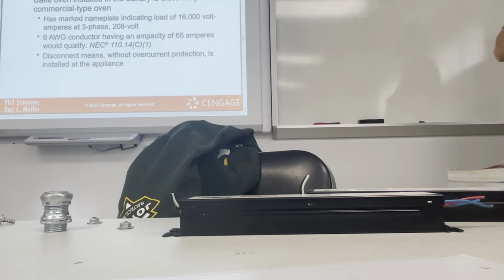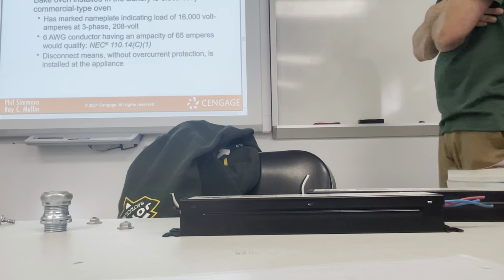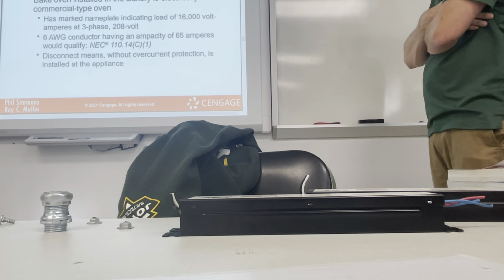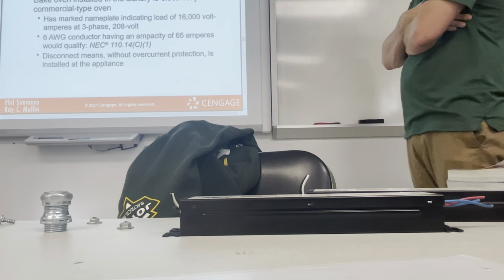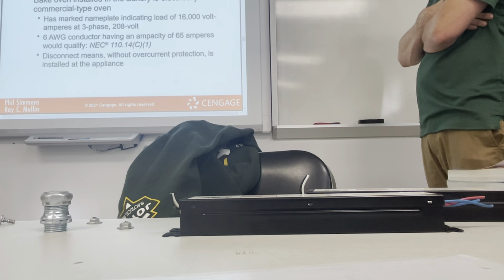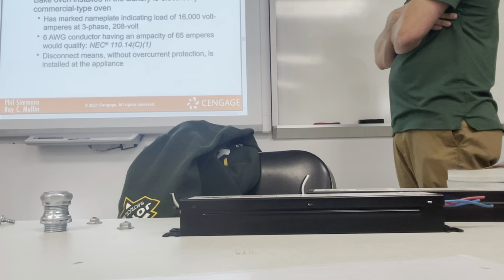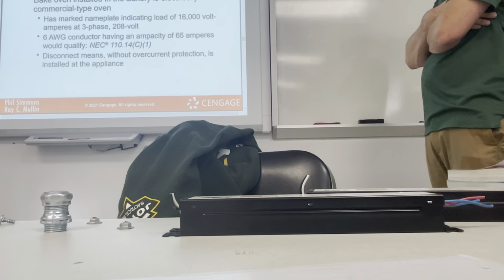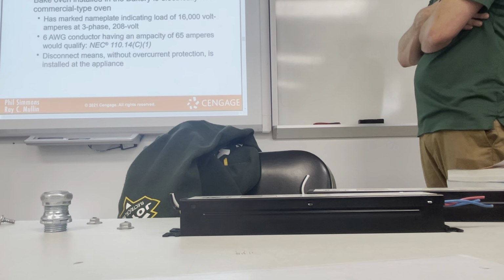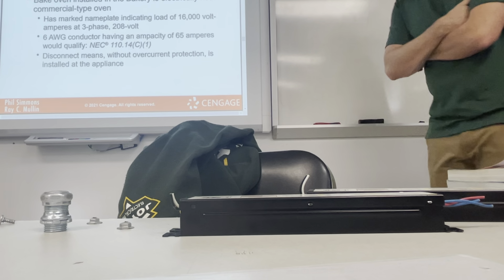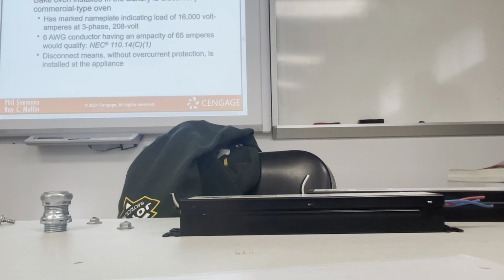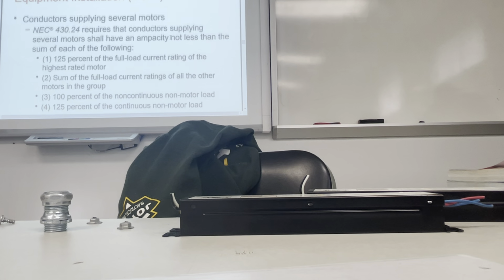Supplying a specified load. A bake oven installed in a bakery is an electrically heated commercial type oven with a nameplate indicating a load of 16,000 volt-amperes at 3-phase, 208 volt. A 6-gauge conductor having an ampacity of 65 amperes would qualify. NEC 110.14(C)(1). Disconnect means without overcurrent protection is installed at the appliance.